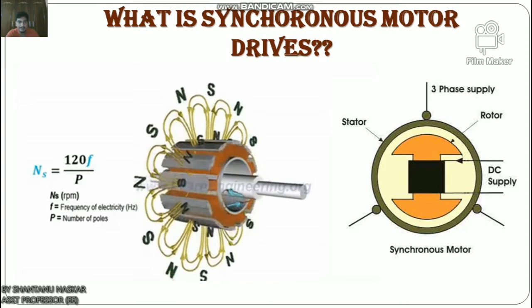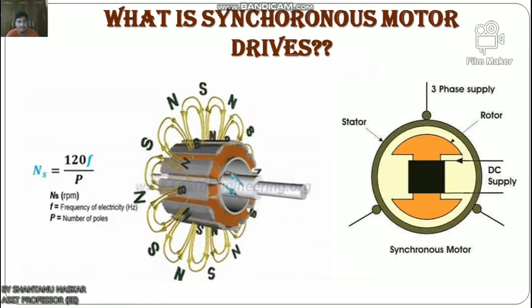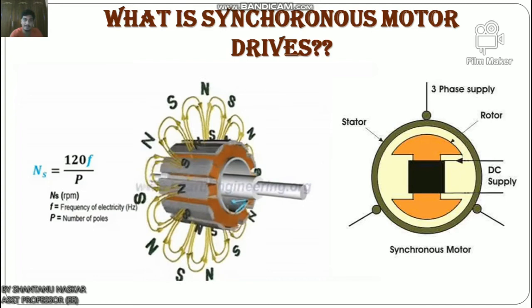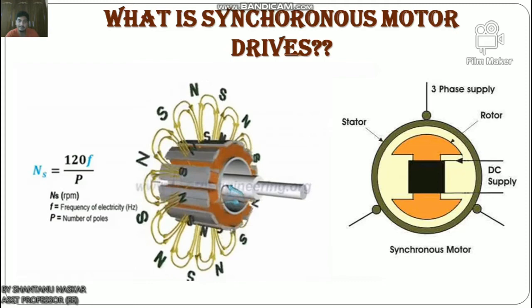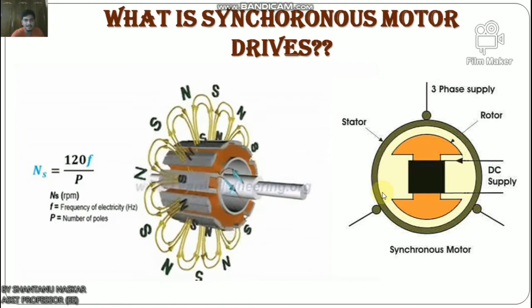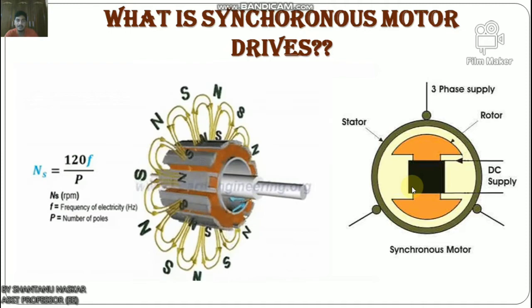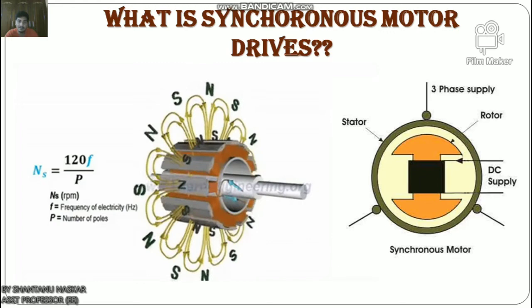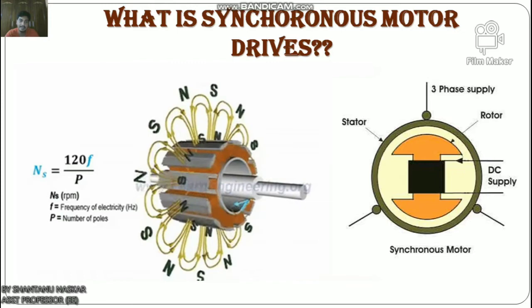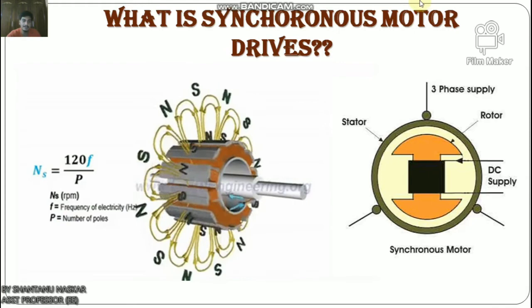This is the reason why synchronous motors are not self-starting. The first starting method is to start the synchronous motor as a normal induction motor — the rotor is not given DC supply initially. When the motor reaches near synchronous speed, pull-in takes place. Another method is starting by an external motor: the rotor is rotated by an external motor, and when the speed reaches near synchronous speed, the DC field is switched on and pull-in takes place. This method has very low starting torque and is not popular.